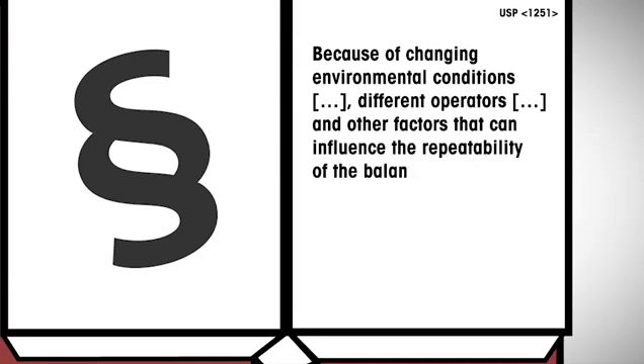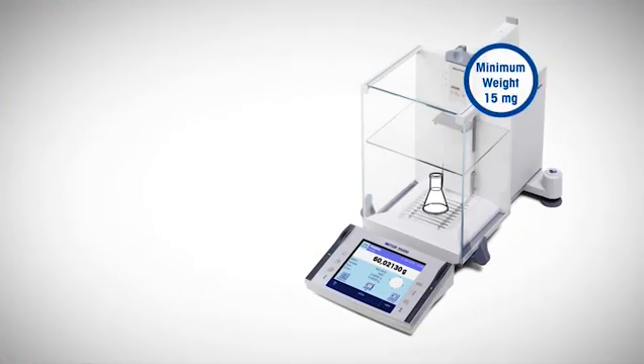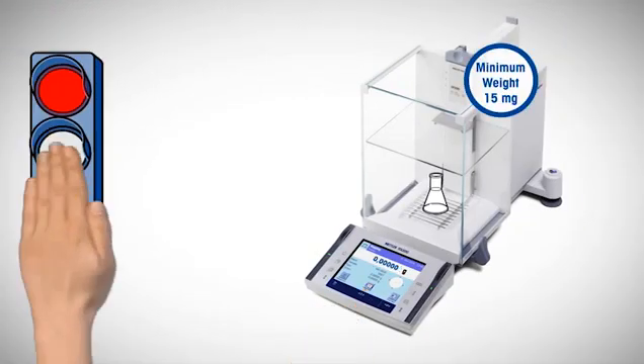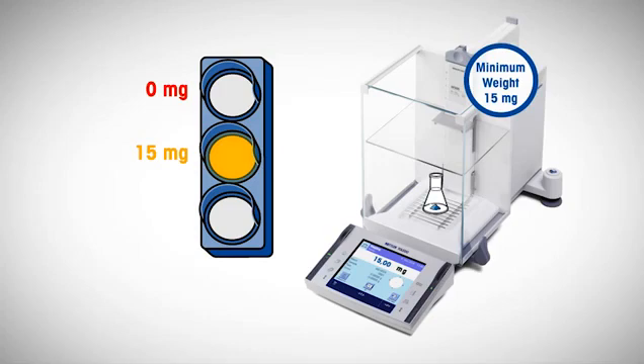Because of changing environmental conditions, different operators and other factors that can influence the repeatability of the balance while in use, when possible, weighing should be made at larger values than the minimum weight. It is therefore recommended to use a safety factor, which ensures that the smallest net weight is sufficiently larger than the minimum weight determined at a particular time by a particular person.